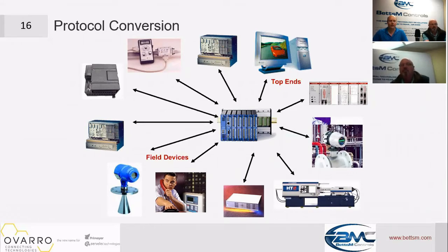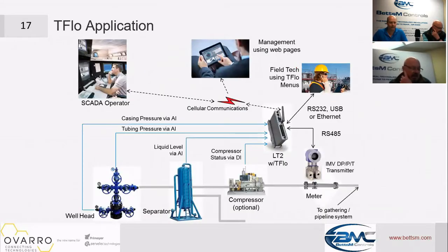Basically, we can take ROC or the ControlLogix PLC or any of those Modbus devices and bring them through the TBox, convert them to MQTT or DNP3, and push the data out. Not only do we locally archive data, so that if you ever have a communication breakdown you can get the data from the device, but we also allow a protocol translation to occur.